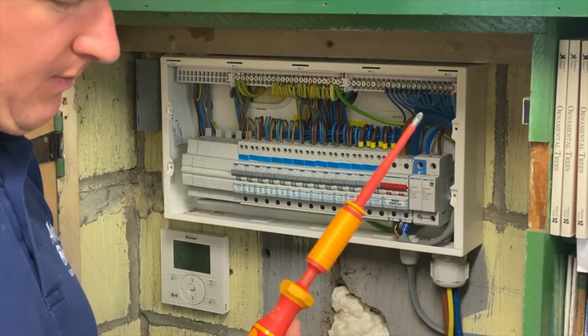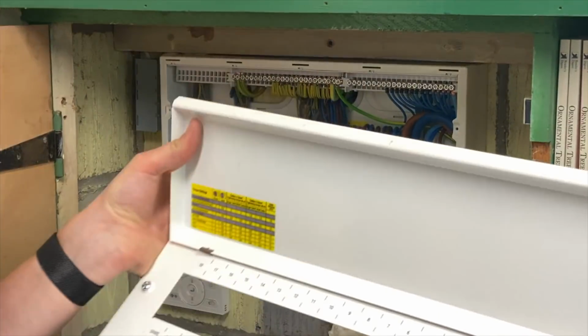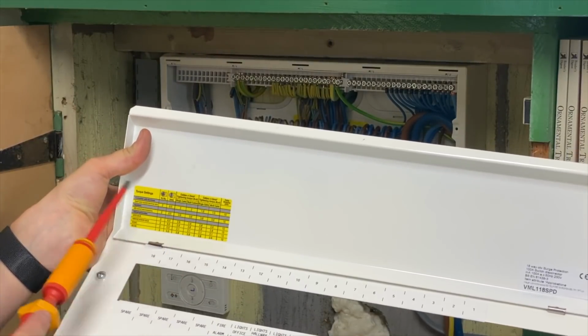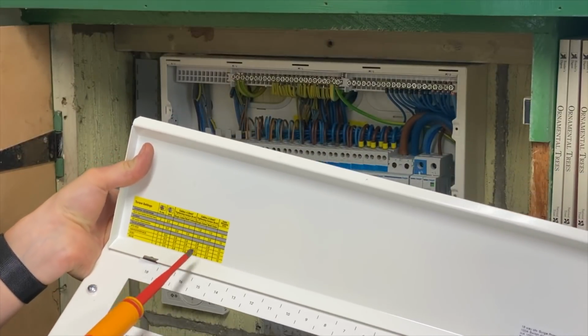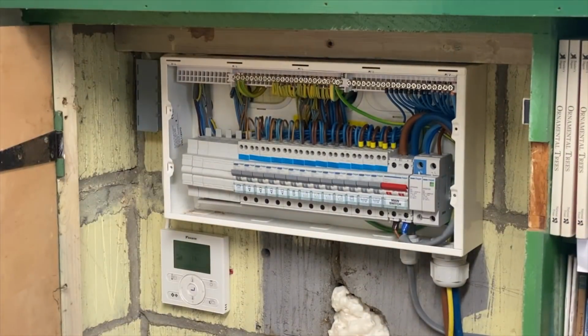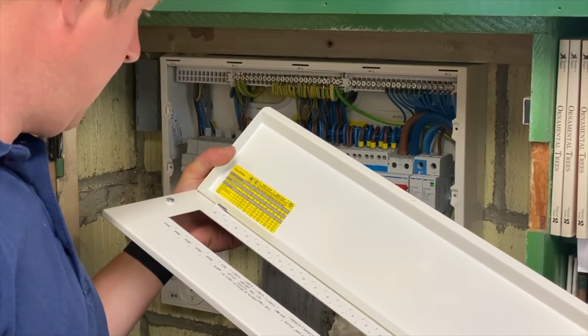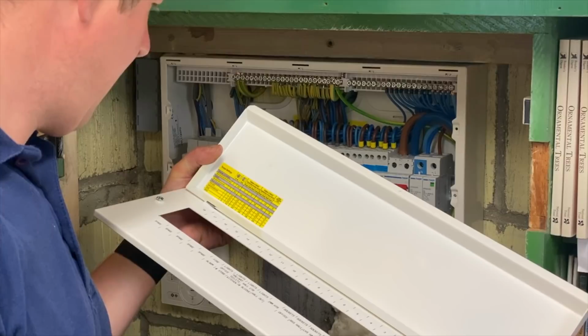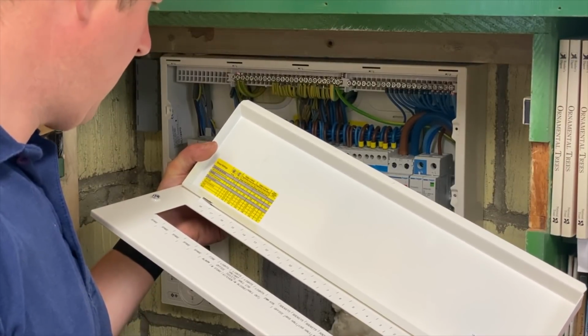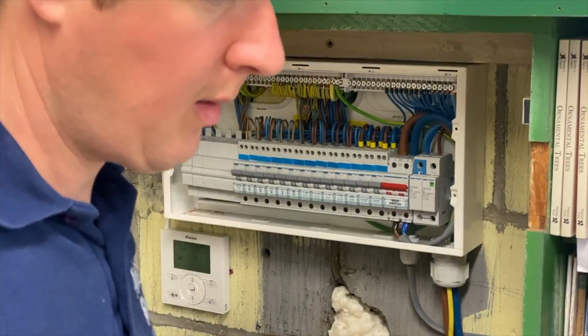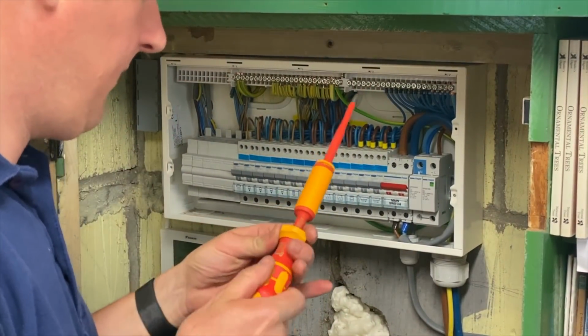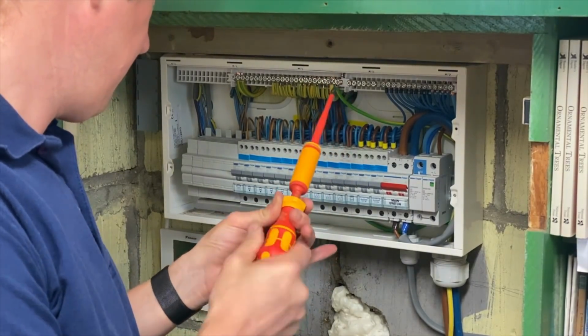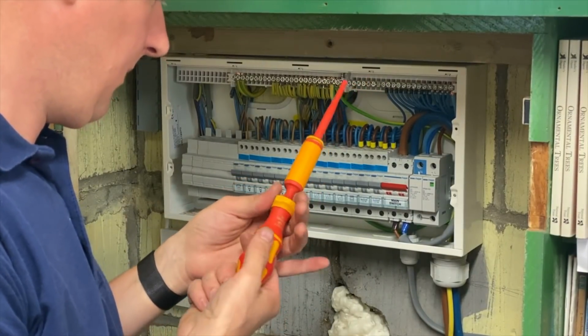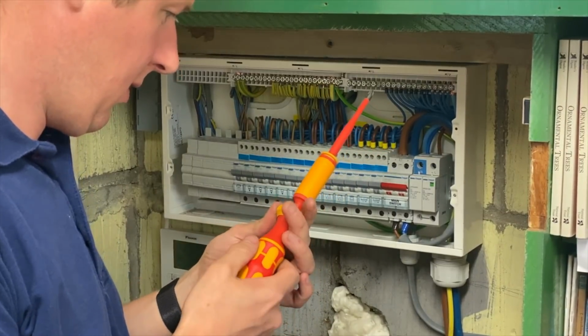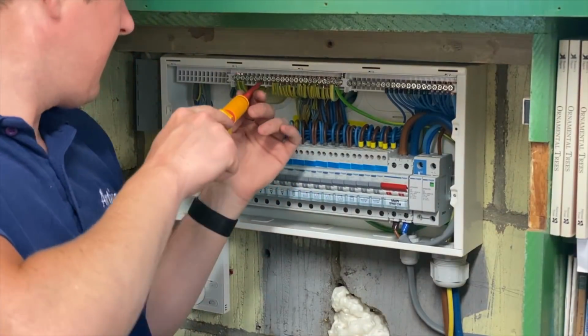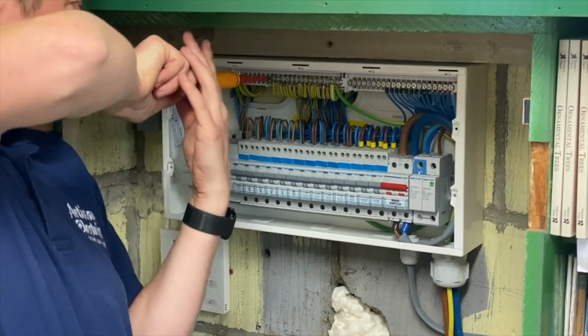So I've got this Wera torque screwdriver, and on the cover of the consumer unit here it has the torque settings recorded for us. So all we need to do is copy the readings from here onto the screwdriver and then tighten up the correct terminals to the correct tightness. So it starts with the earth and neutral bars, PZ2, cables greater than 1.5mm should be tightened to 2Nm, and cables less than 1.5mm to 1.5Nm. So I'll start with 1.5Nm on here. Nm stands for Newton meters, by the way, that's a torque measurement. Go all the way down to 1.5, which seems quite low. There we go. So, any conductors less than 1.5mm, which are basically the lighting ones.